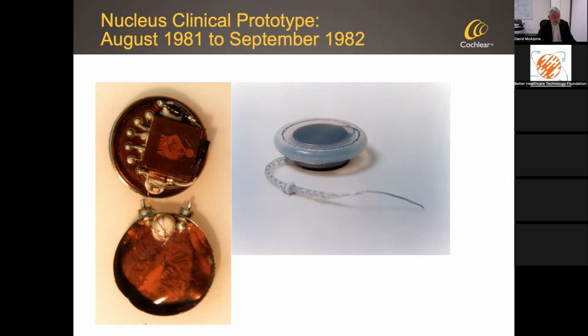We used just a single integrated circuit, which you can see in here, which is effectively implanted then into 2 hermetic enclosures, one inside the other. We have 24 feed-throughs, many more feed-throughs than the pacemakers have, and it used an internal transformer to keep the external voltages to the coil to be very low. Damage as a result of electrolytic corrosion was a big issue for one of the Melbourne devices.